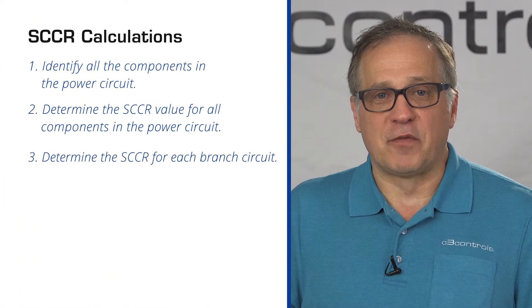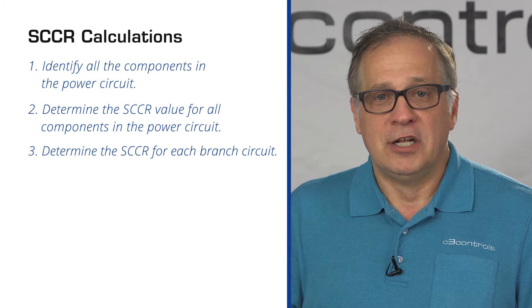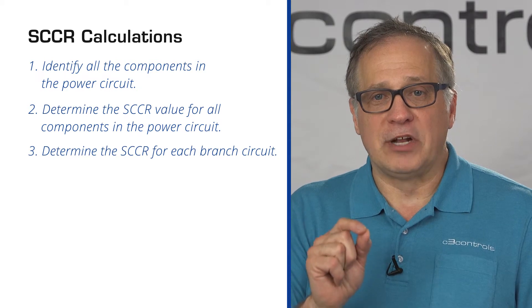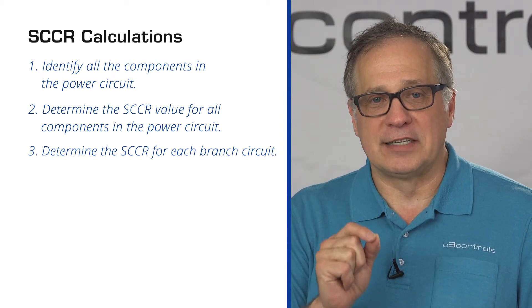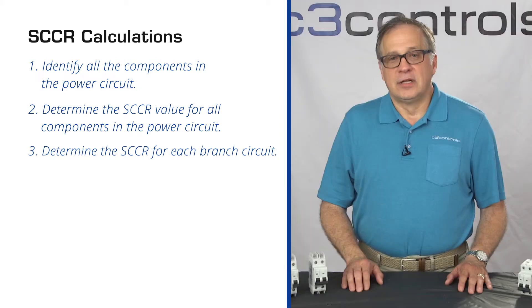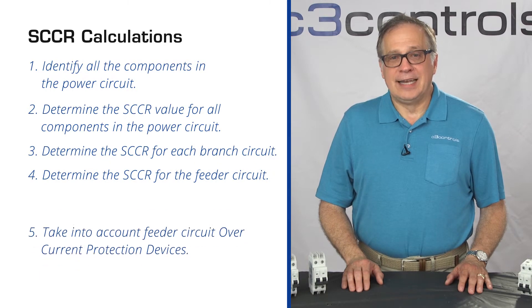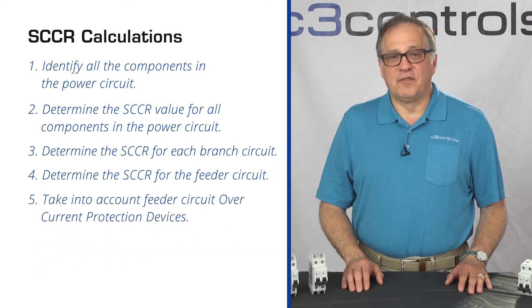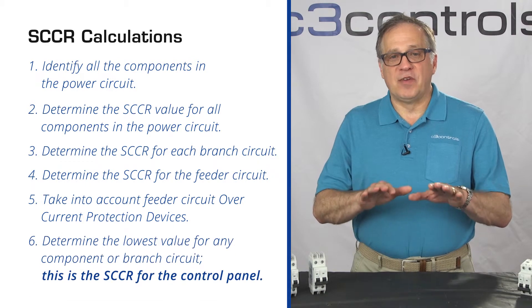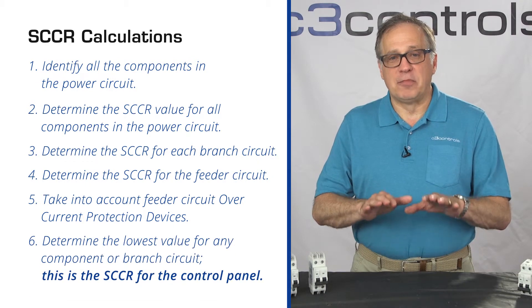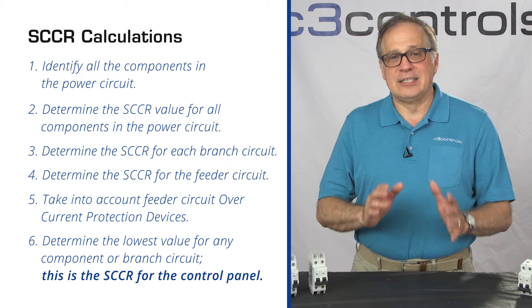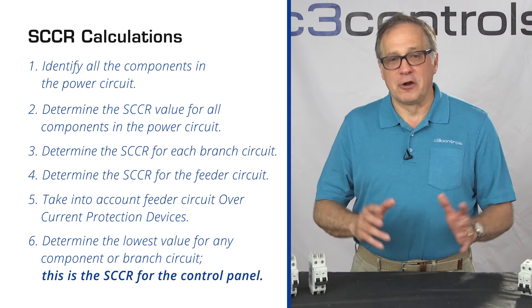Then we determine the SCCR for each branch circuit — the lowest component SCCR is the branch circuit SCCR. Next, determine the SCCR for the feeder circuit, taking into account the feeder circuit overcurrent protection devices. Determine the lowest value for any component or branch circuit; this is the SCCR for the control panel.